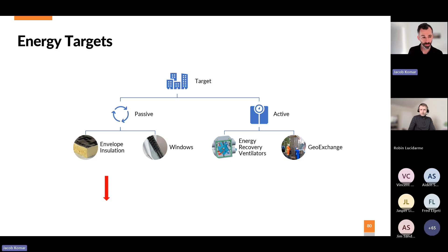If you're not familiar, ground source heat pumps are geothermal systems. It's basically where you take advantage of the stable earth temperature. Below the frost line, this earth temperature is basically stable year round. In Edmonton, it's about 7 degrees year round. And we install a heat exchanger, either vertical or horizontal, and you can also use a pond or an aquifer as a source, but most common is a vertical heat exchanger where we circulate fluid through the ground and we pull heat from the ground in heating and we reject heat into the ground in cooling.